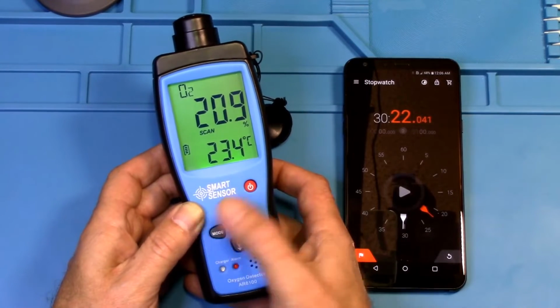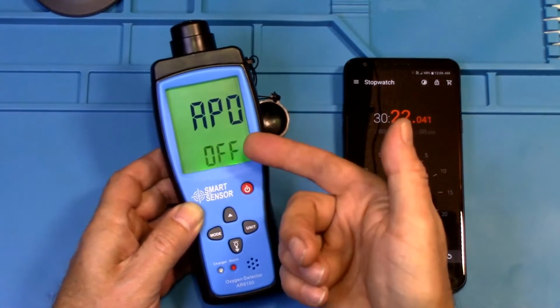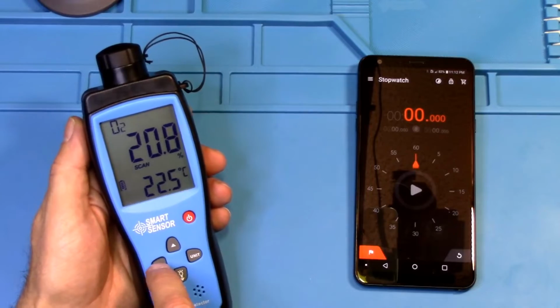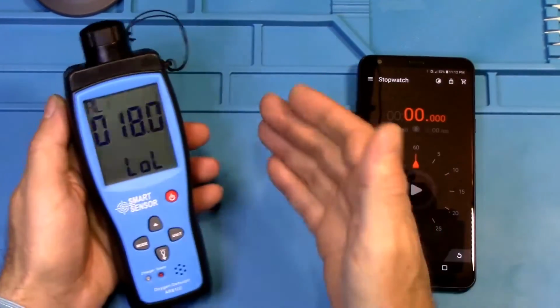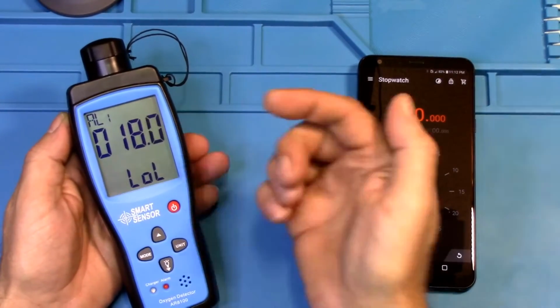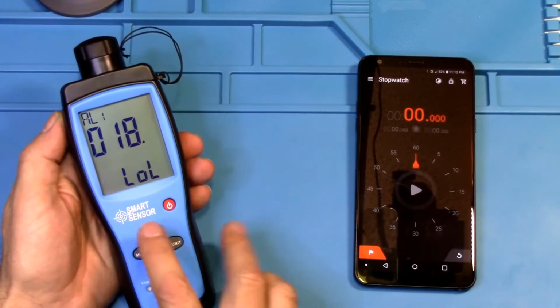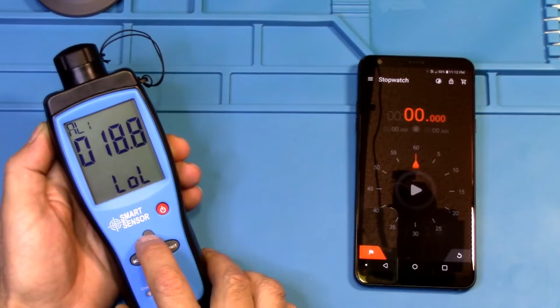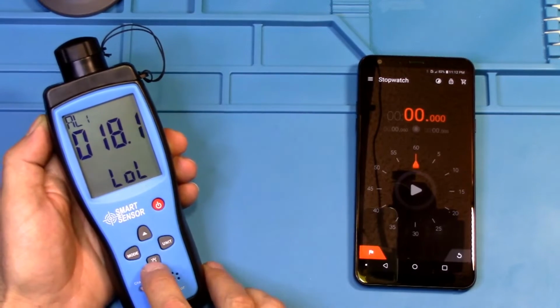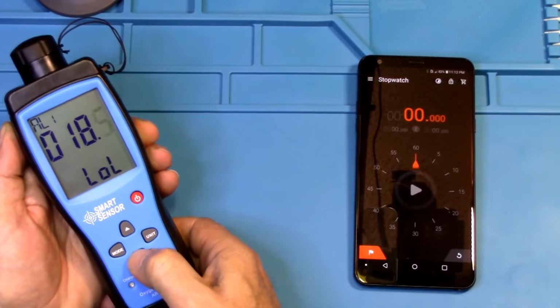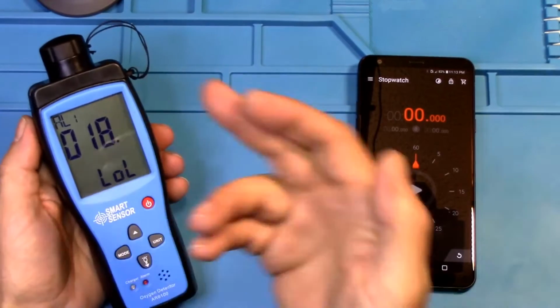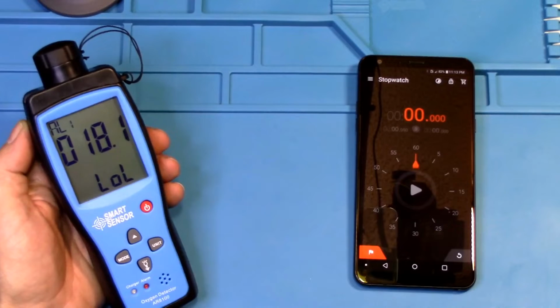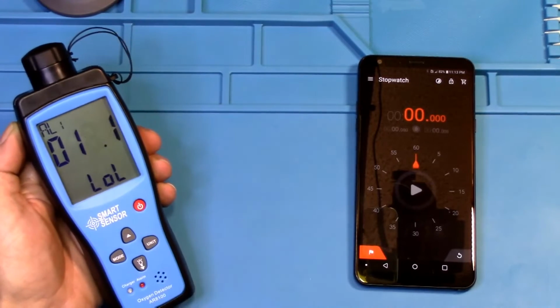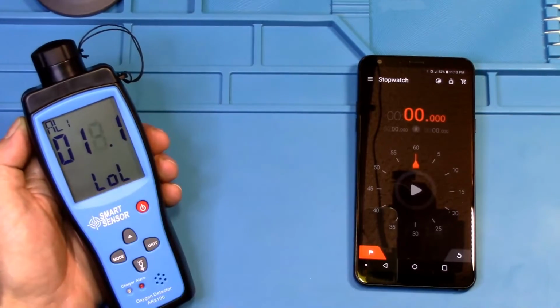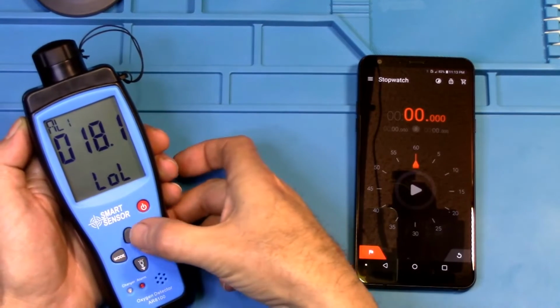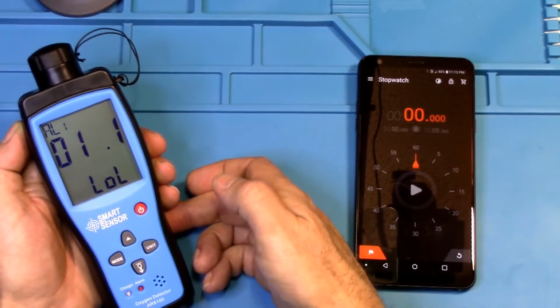And just to be sure, you can press and hold the mode button again just to make sure it took, and it did. It's set to off. Okay, hit the mode button quickly to go into AL1, alarm 1. Now what you do is, see this number is flashing. You press the up or the down arrow to make that number go up to 9, and it'll start back over at 0. Hit the down arrow button to go down. Okay, and if you want to set this at, say, 17.1, to move to the 8 digit there, press the unit button, and that will back up to the next number down the line. Then again, you use the up arrow or the down arrow to change what that number is. And now it's saying 17.1.